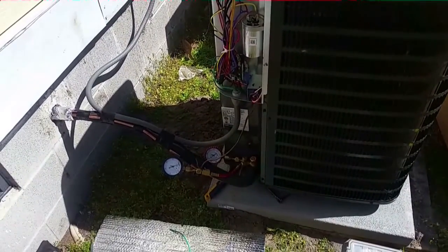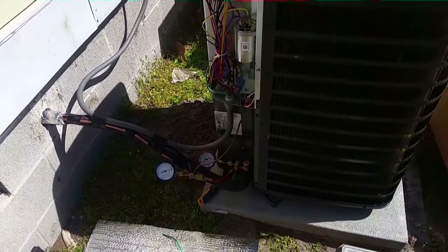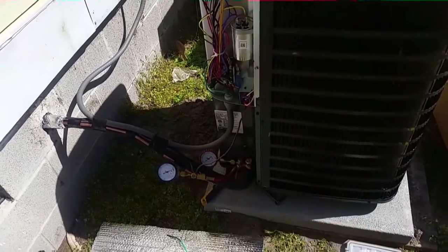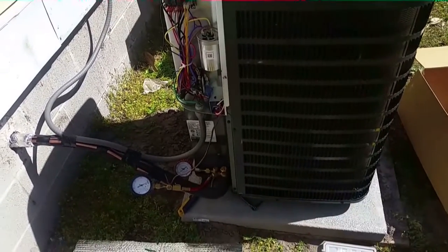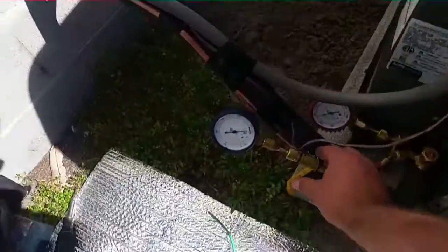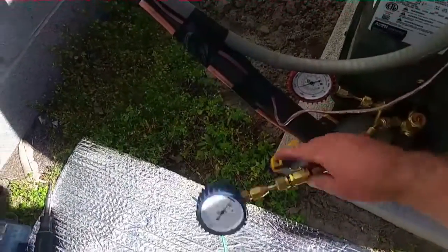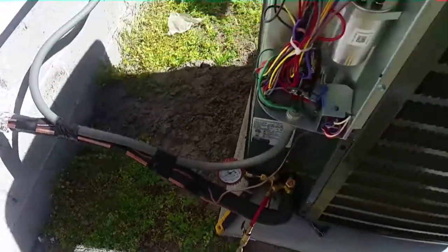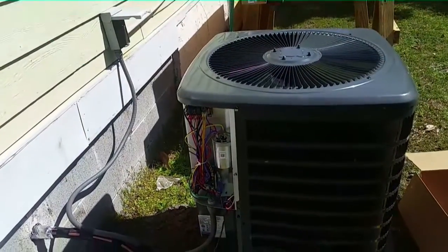Alright guys, so we have 680 CFM running through our system. We're letting it run in heat for a little while. I'm an idiot. I put the wrong gauge on the wrong one because I'm going to run it in cooling here in a minute. Probably shut it off. There. I'm going to switch it to cooling once it warms up inside a little bit.